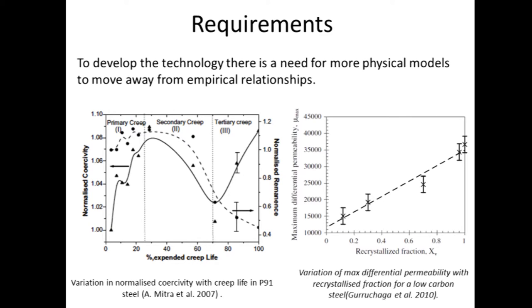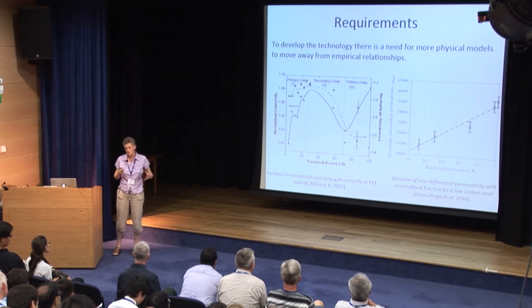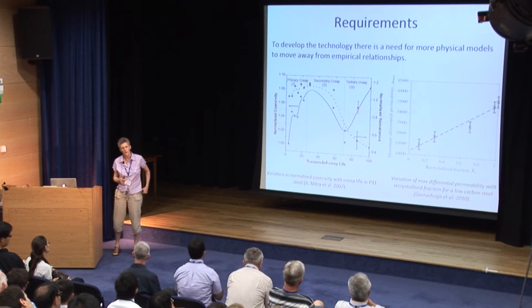The kinds of things that can be done already — I've put some examples up here — there are relationships in the literature between a magnetic or electromagnetic property and either mechanical property information, such as creep life, or microstructural information measured by other techniques such as metallography or recrystallized fraction. There's quite a lot of lab-based tests that can do that, but in order to have something more generically useful — so somebody can use it with different steel types without lots of calibration samples, which is where we currently sit — we need to take this a little bit further.